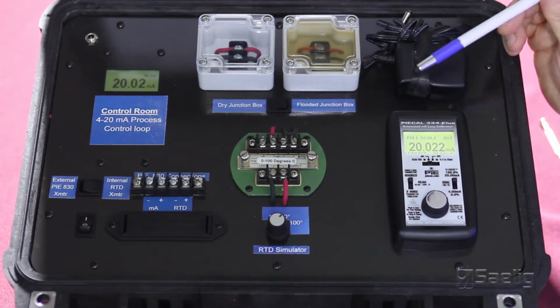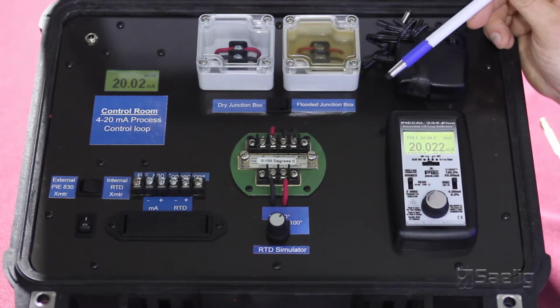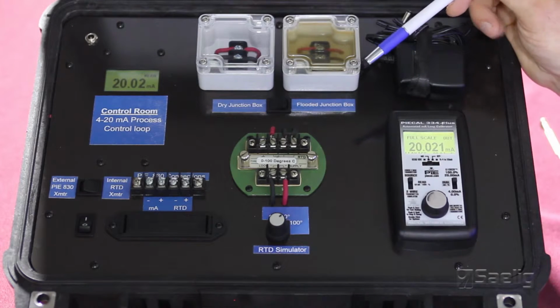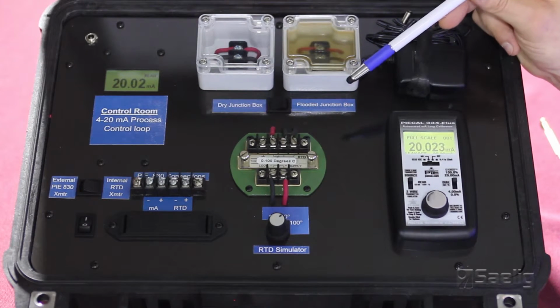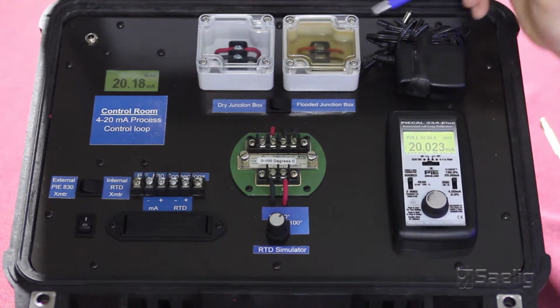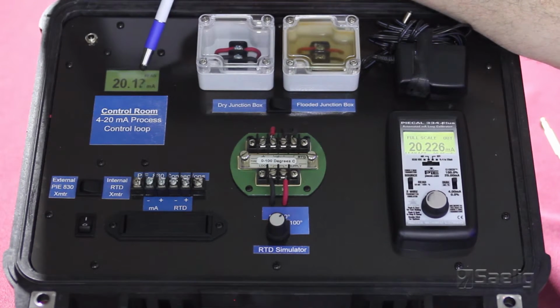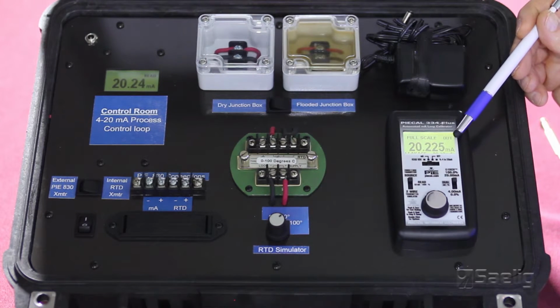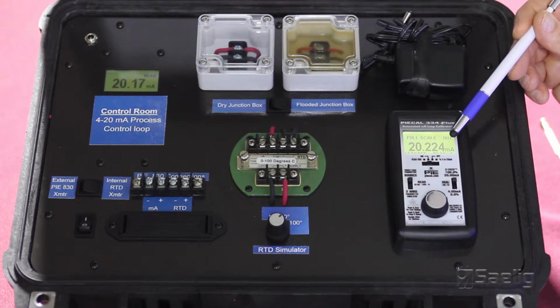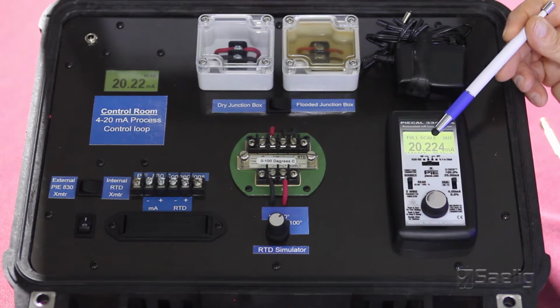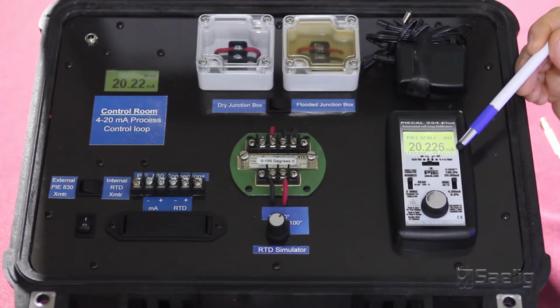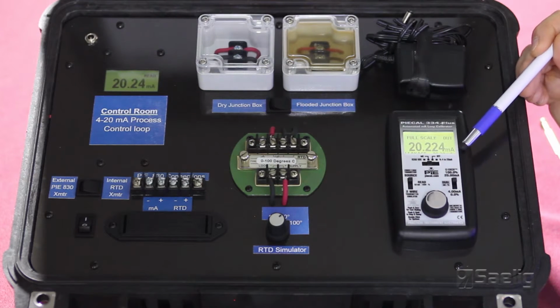Now, what happens if we introduce moisture or condensation in a junction box or into conduit, say after a heavy rain or humidity conditions in the south? The control room sees a problem and a technician will be dispatched to find out what the issue is with the loop. We now have about 0.2 milliamps of uncontrolled current being seen at the control room. The PIE 334 Plus is also displaying the same measurement as an output of the transmitter of 0.224 over the expected 20 milliamps, and the leakage current now is also being displayed, 0.22 milliamps.